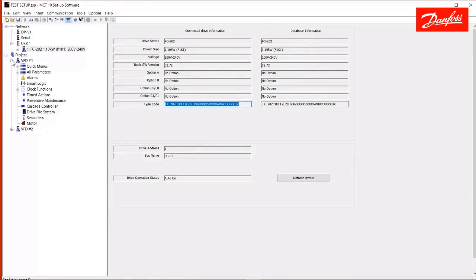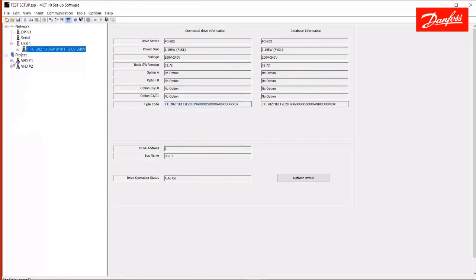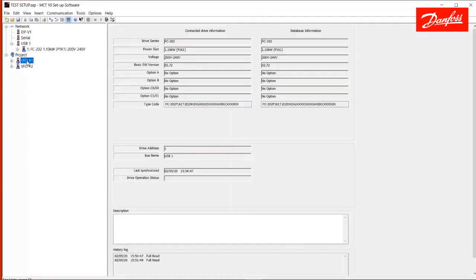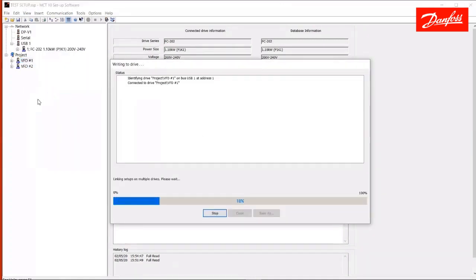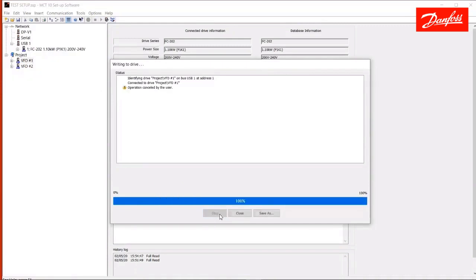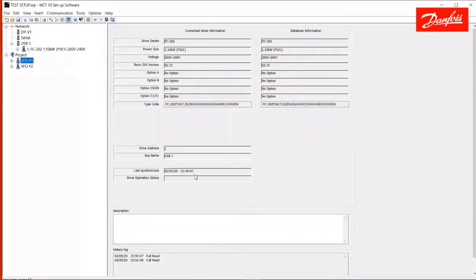Another thing we can do on the project side is create generic drives. Before I get into that, I'll show you, if I wanted to have the change that I made in this project drive be written to the live drive, I can right click and say write to drive. I'm going to go ahead and stop that there. That would have written that one parameter change into that drive. Again, we're offline here, so unless I initiate that write, this drive is not affected.